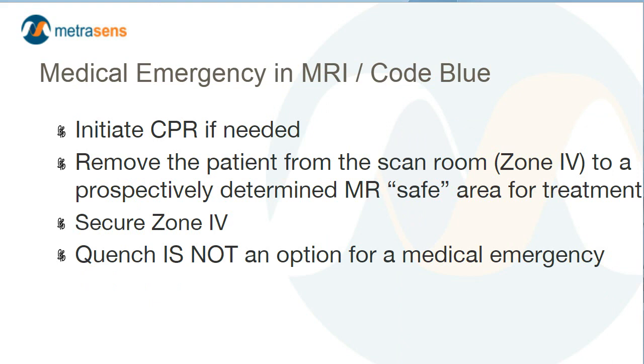In the event of a severe medical emergency, such as cardiac or respiratory arrest, the ACR recommends beginning CPR while removing the patient from Zone 4 to a prospectively determined MR-safe area for treatment. If the area is in Zone 3, the door to the scan room should be secured or locked so that responding non-MRI personnel cannot inadvertently enter Zone 4. It's important that the patient be removed from Zone 4 before responding non-MR personnel arrive. Quenching the magnet is not an option for a medical emergency.